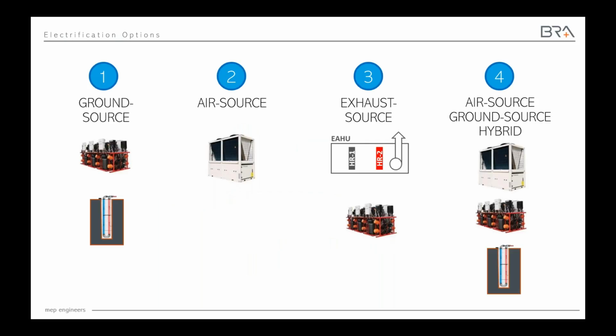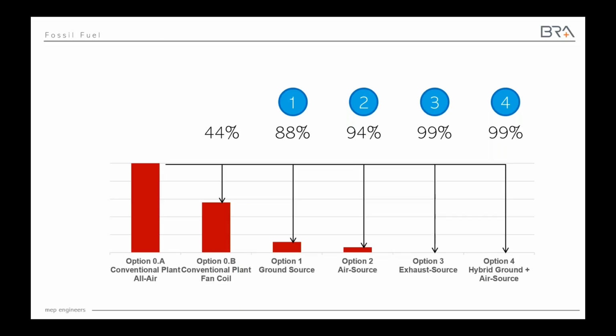Now, we did look at a series of different solutions like we do on all projects, to make sure we're advising our clients and they're making a wise decision financially. So we looked at ground source in option 1, we looked at air source in option 2, we looked at exhaust source in 3, and then we looked at hybrid options in 4 and a few others. On the next slide, you can see all of these get to these incredible reductions in fossil fuel consumption. But it's interesting to see that the ground source, which people often think of as the ultimate for fossil fuel-free buildings, when you have a building that's so high energy as a lab building and has these huge peak loads, there's no way you're going to get a bore field big enough in a dense urban environment to handle the peak loads. And so because of those limitations, we couldn't quite get to the 90% fossil fuel reduction mark with the ground source alone.